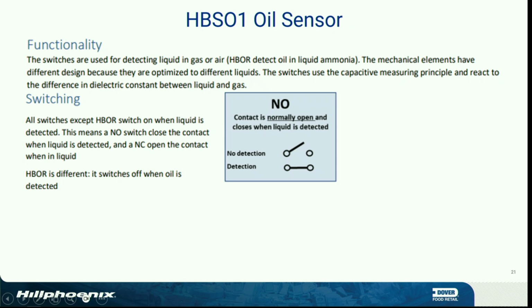HBOR is different. It switches off when the oil is detected. And again, the only place we'd really use a switch that switches off would be in our liquid detection for high level, or liquid and any oil or liquid you might get in your suction accumulator. You want to protect your compressors. We've used them in series, so we'd actually shut down the system, run the suction accumulator, pump them out, and then turn the system back on.